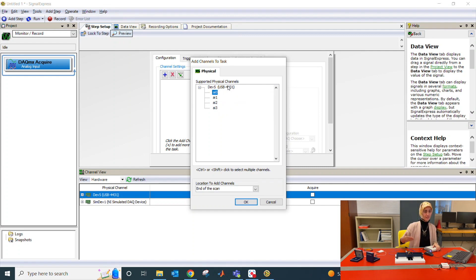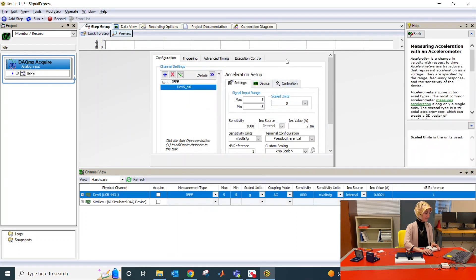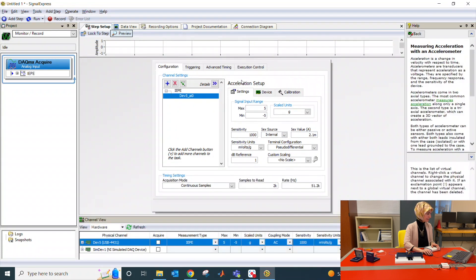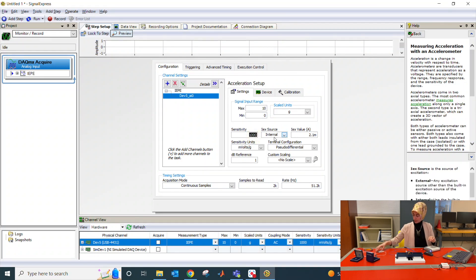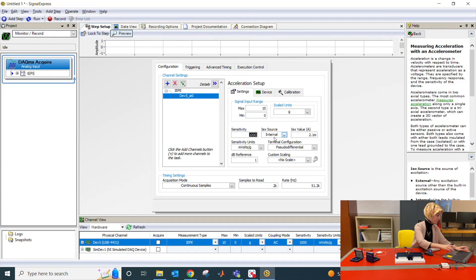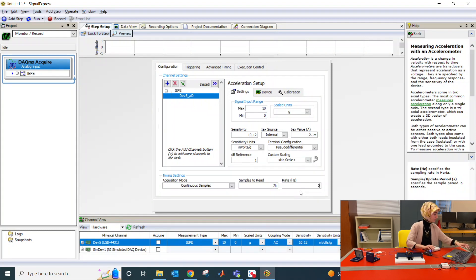If you had multiple sensors connected to your system, you can select channel zero, channel one, and channel two. But today I'm only reading from one channel, so I only selected channel zero. Just click OK after. Now we have to adjust the settings: your minimum value will be zero and the maximum will be 10. The sensitivity — let me double check — in the X direction from the data spec sheet it's 10.12 millivolts per G. The unit is correct. Samples to read is 2K, and you may want to change the rate to also 2K.